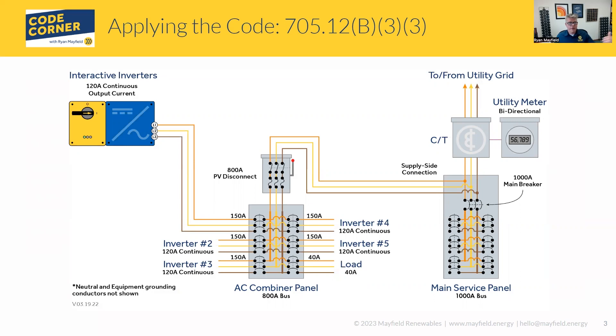What we have in this case is a commercial system with multiple — in this case five different inverters — and we're wanting to interconnect those. We see that we have a supply side connection, and for our interconnection to the utility. But what we're looking at here is this AC combiner panel. What this code section 705.12 B33 is saying is that the sum of the breakers — both source and loads — cannot exceed the bus bar rating. So if you look at all five inverters, the rating of those breakers is 150 amps each, so we have 750 amps of source in this case. We have a load showing 40 amps. Add all those together: 790 amps — we are under the 800 amp bus bar rating. We could actually have a 50 amp load and still be in compliance. So we can have up to 800 amps worth of breakers inside that panel.